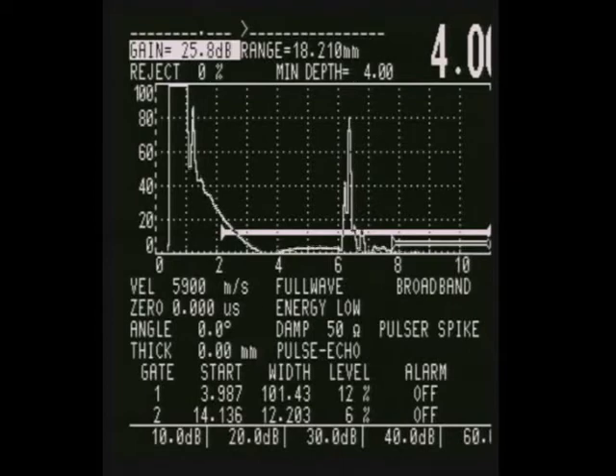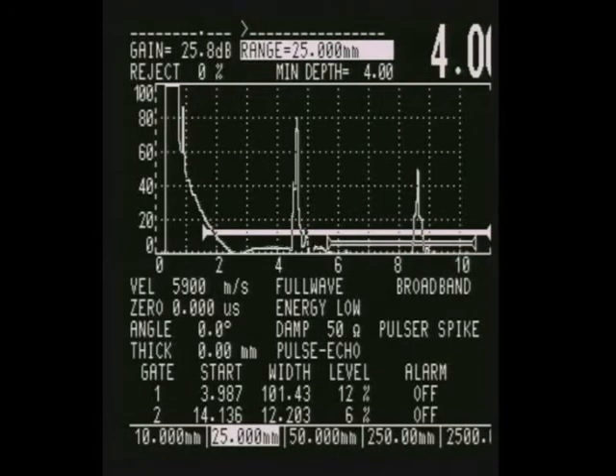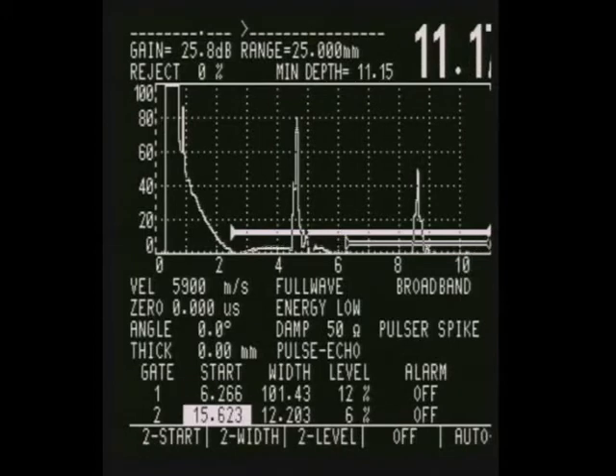Bring the gain down a bit. I usually like to have my echoes at about 80%. I'm going to range out to 25mm so I can see two or more echoes. Bring my gate back and my second gate.